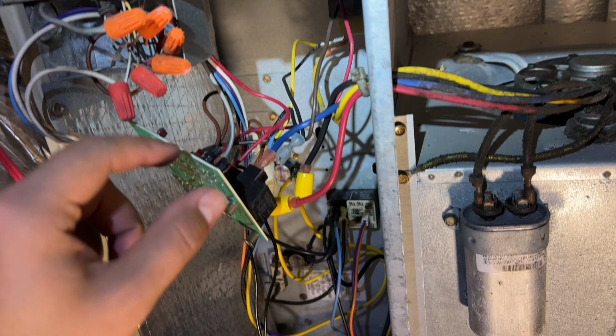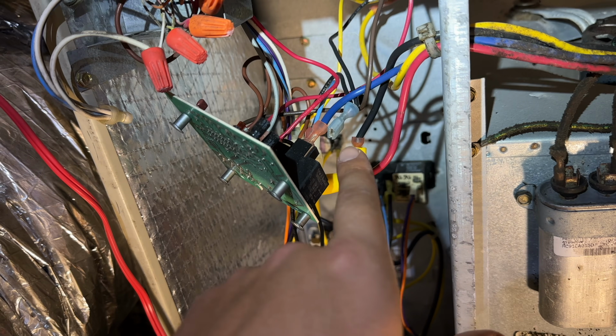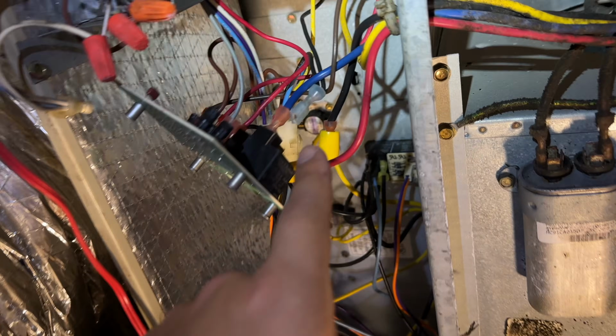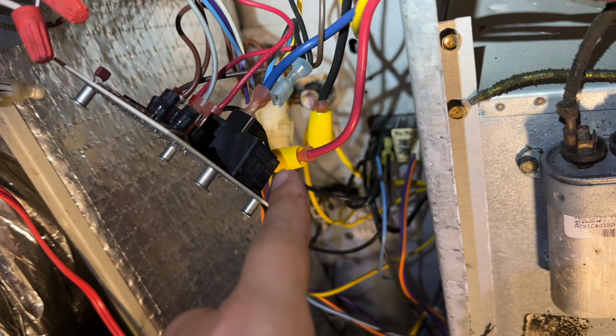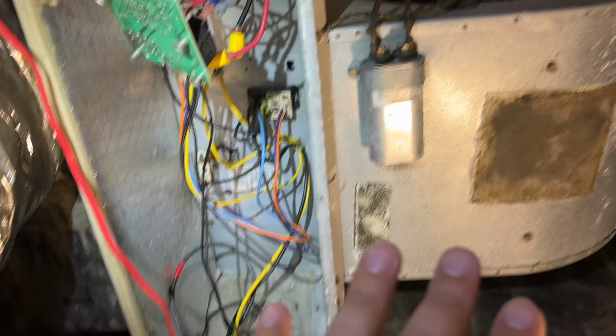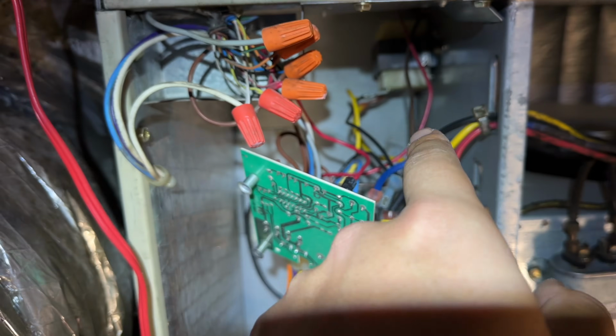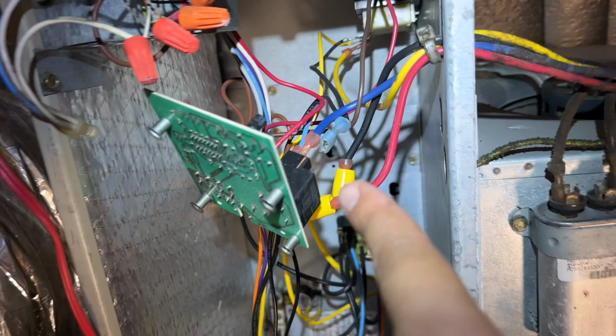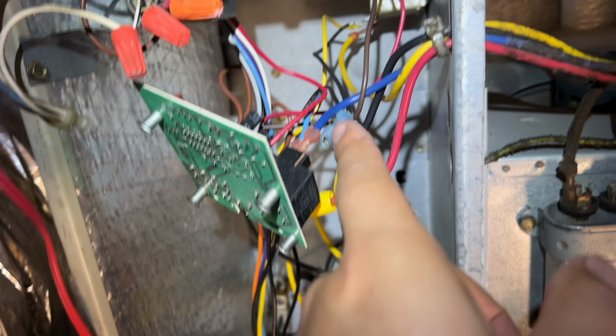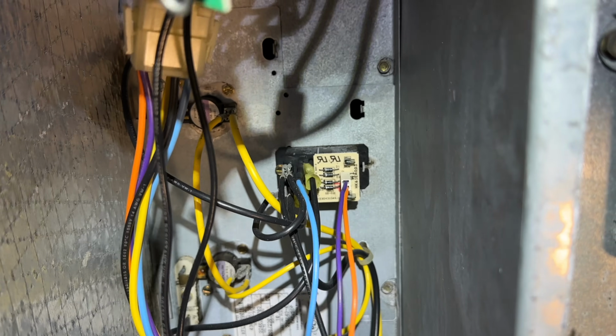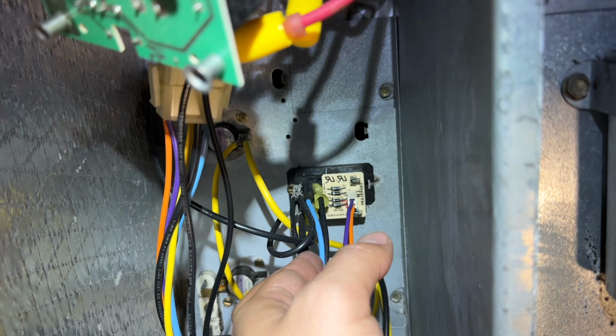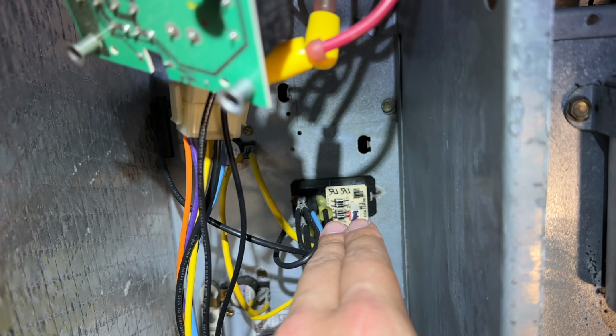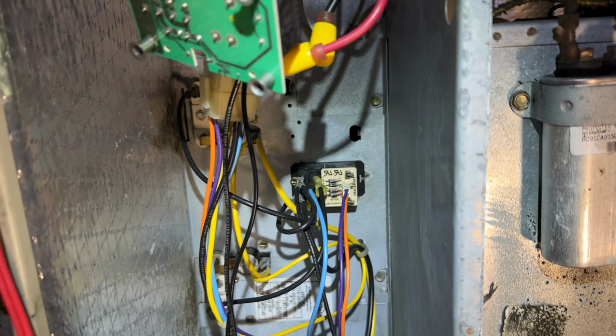All right, so I disconnected this black wire from this relay, and it seems to be working fine right now. It hasn't tripped, but that black wire comes from the transformer, runs to the board, and then from the board it runs back into this harness here, and from the harness it goes into this relay for the heater. So I'm not sure if that's bad, but check that. That might be bad.